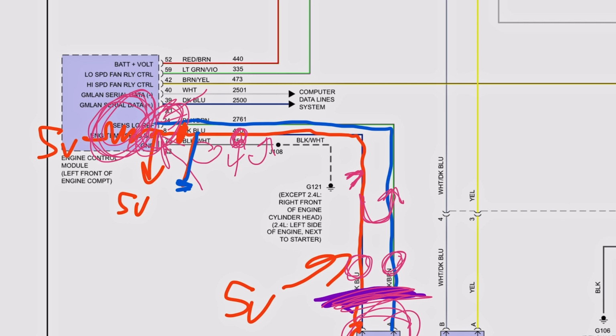If this wire has the capability, while disconnected from your circuit, of carrying that small load, the wire's good. You still have to watch for pin fitment issues, but that eliminates whether it's a problem with the sensor or a problem with the wiring.